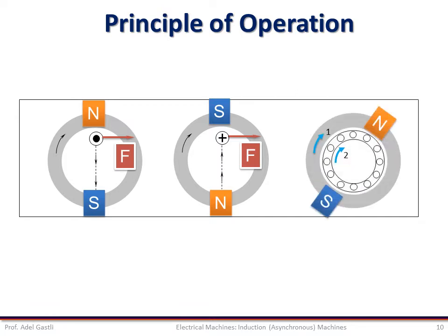So if the whole rotor is placed in the rotating magnetic field, all the rotor rods are thus influenced by forces making the rotor rotate in a certain direction. Notice that the rotor speed will not reach the speed of the rotational field, as no currents are induced in the rotor rods when the speeds are the same.